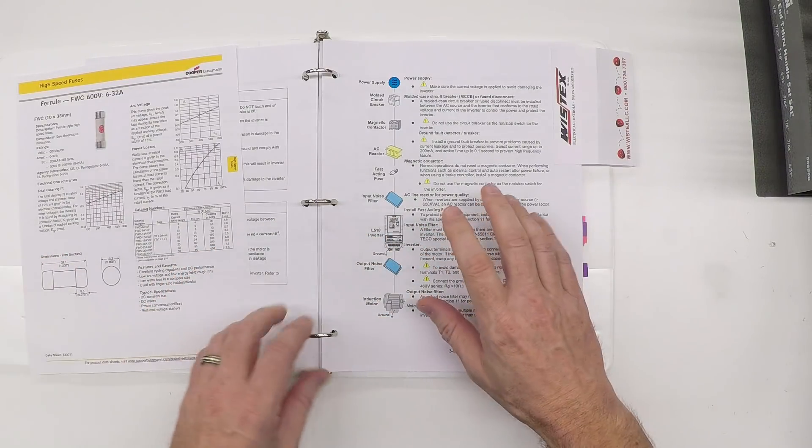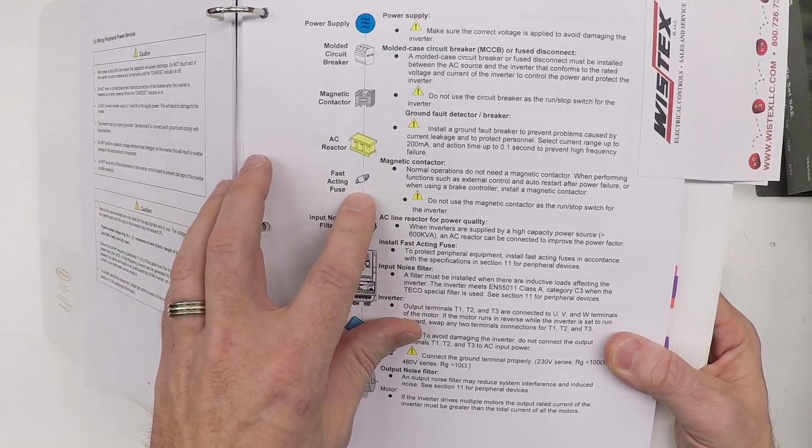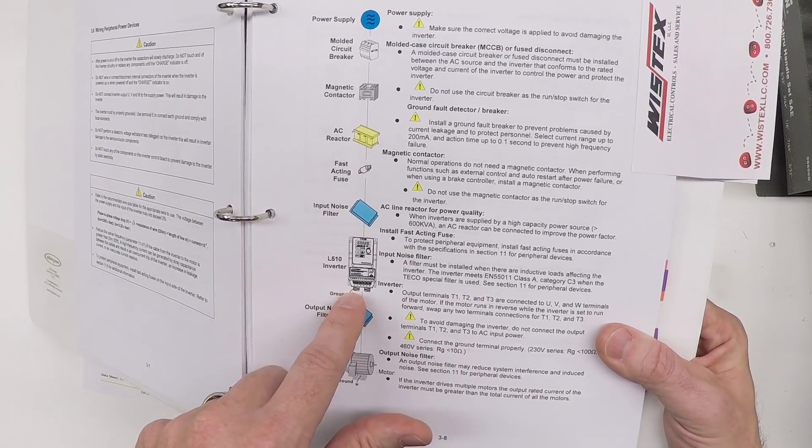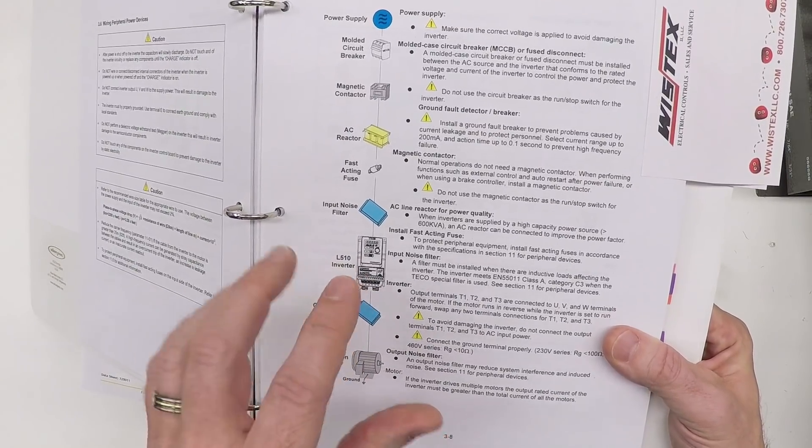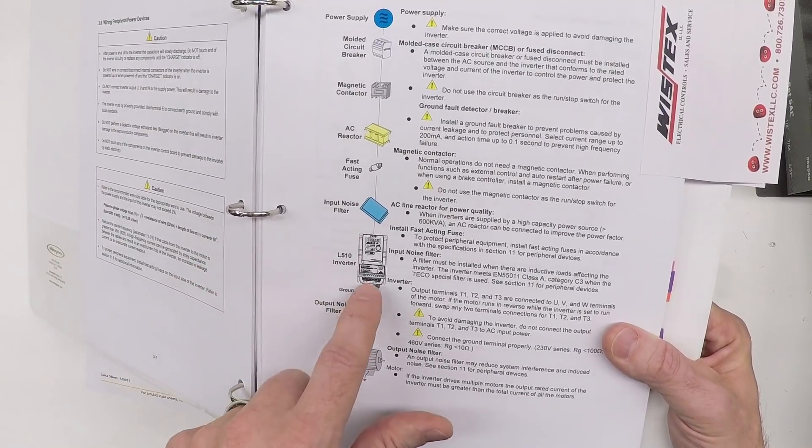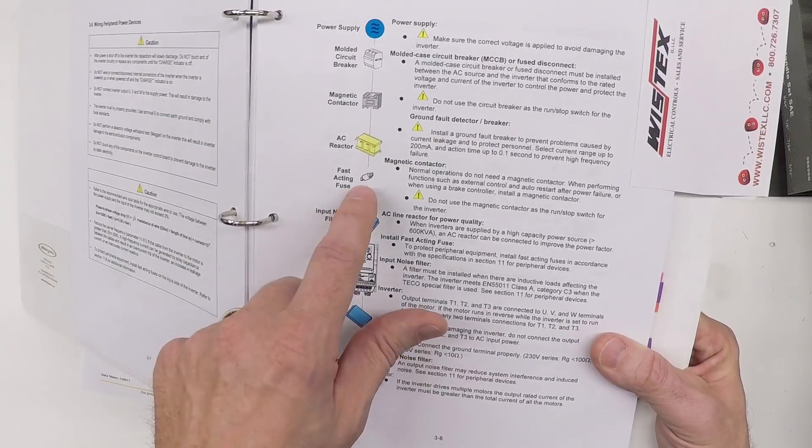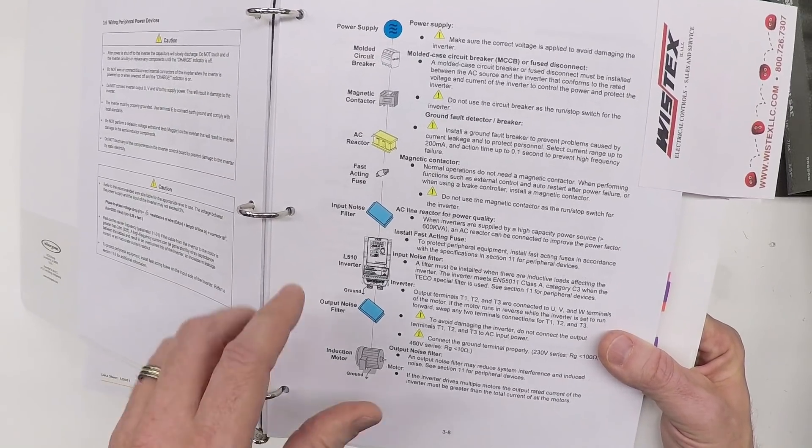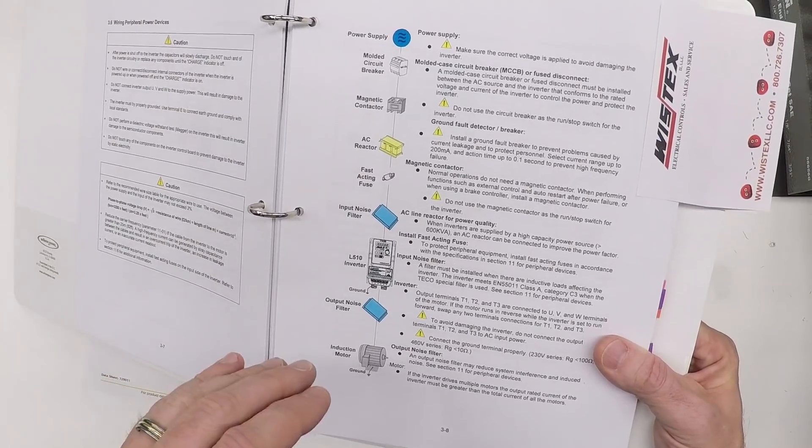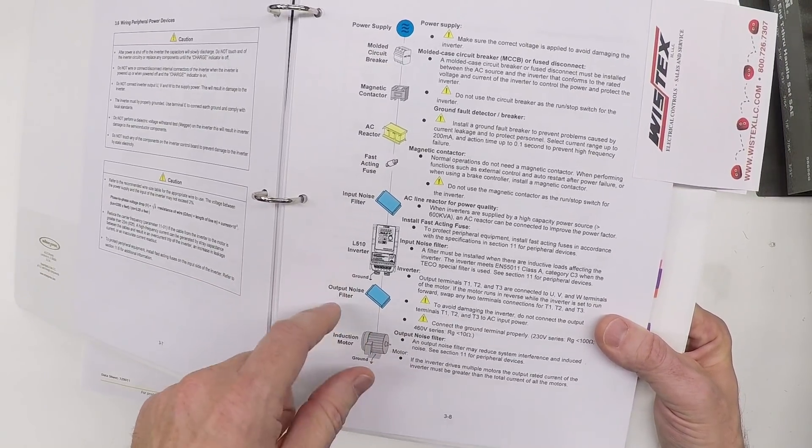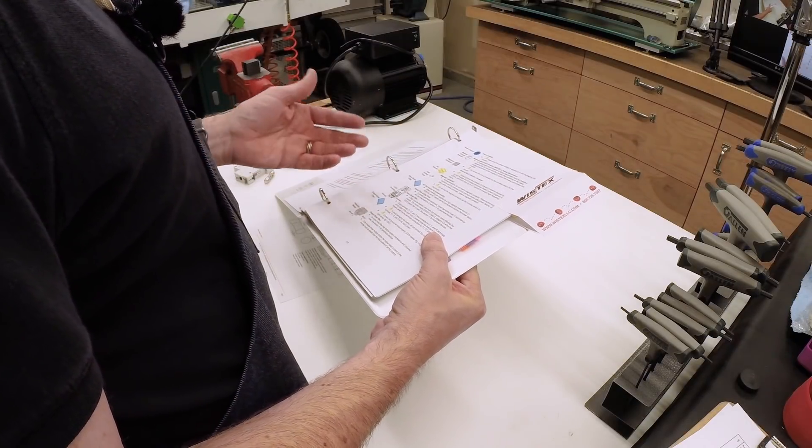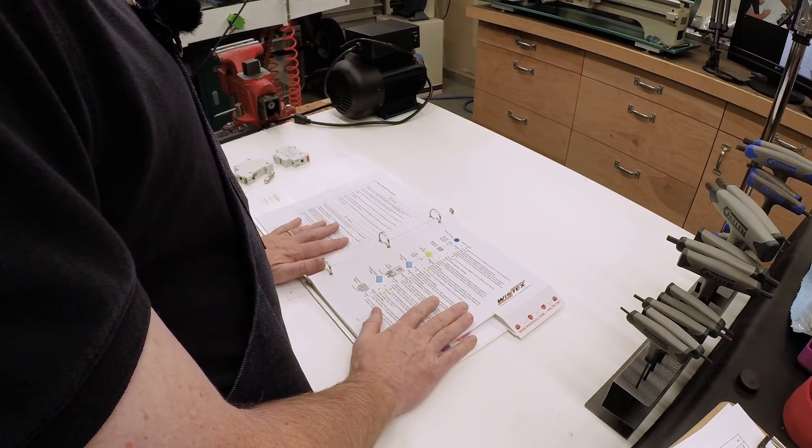The other thing I was able to turn up, I did some reading in the forums about why you would do this and why does the manual call for this. I saw some suggestions that the reason that they call for a fuse is because that's the configuration that they used when they ran this device through safety and compliance testing. This VFD is UL listed, and from everything I've read, it would have been tested by Underwriters Laboratory with this specified fuse in place. There's lots of speculation about what parts were available and could be imported and were suitable for the test rigs. But in the end, it seems to be that this was UL tested with the fuse, so they spec it with the fuse. But in general, the fuse isn't really needed if you've got the circuit breaker. Well, they show it. It's inexpensive. I'll go ahead and put it in. Let's go over the box and take a look at how all this stuff mounts.